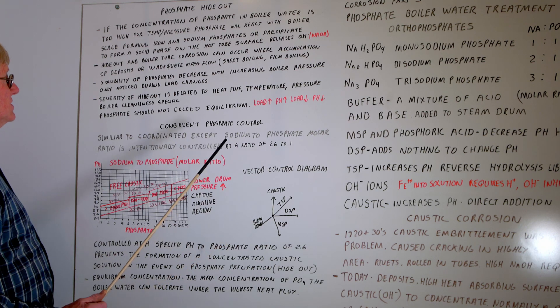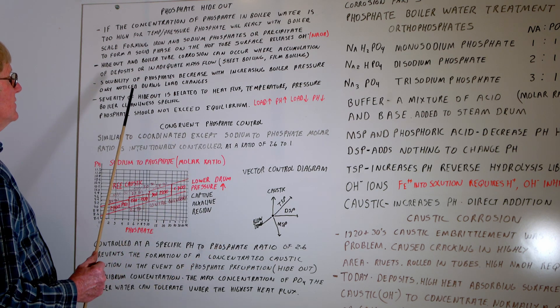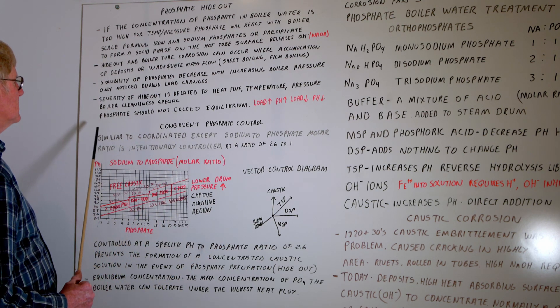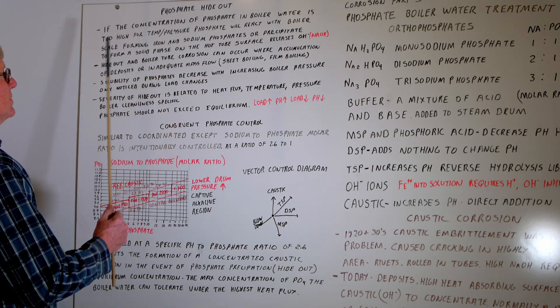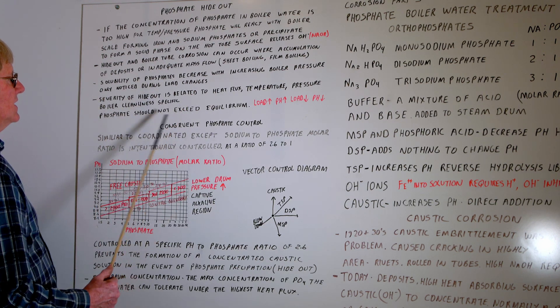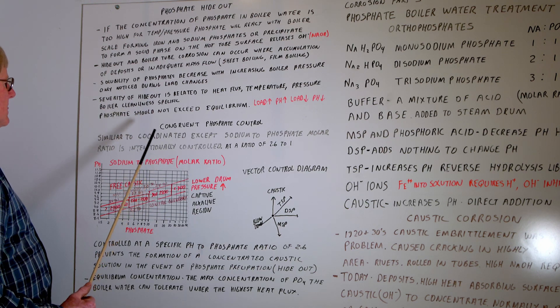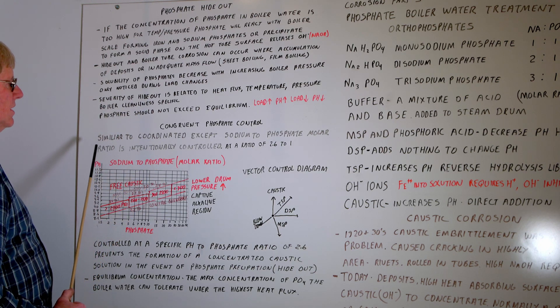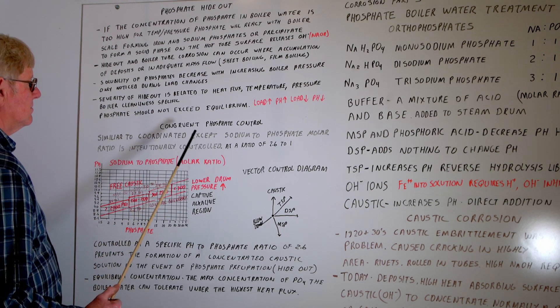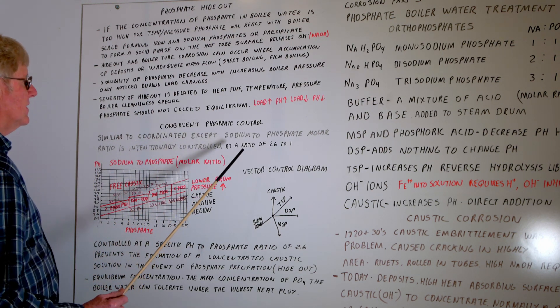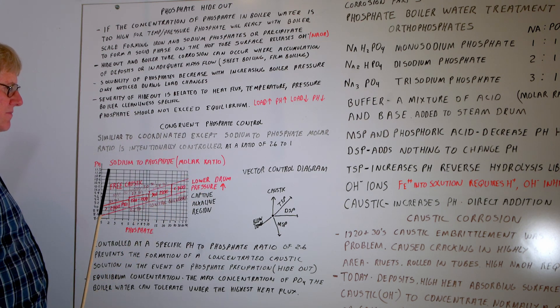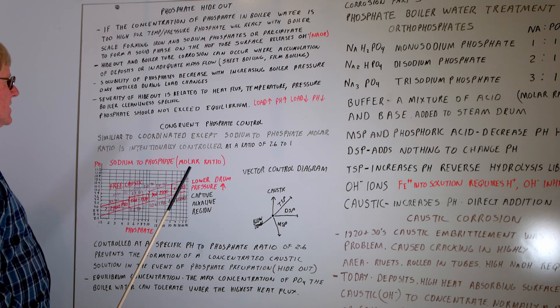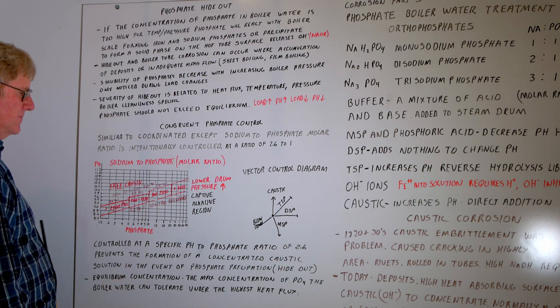This is a very basic overview of phosphate hideout. If anyone uses phosphate in boilers that change load frequently, you're going to experience phosphate hideout. Usually it's not a problem on clean boilers if you control it adequately. But if you don't, it can create problems of tube failures and other issues in the boiler over time.